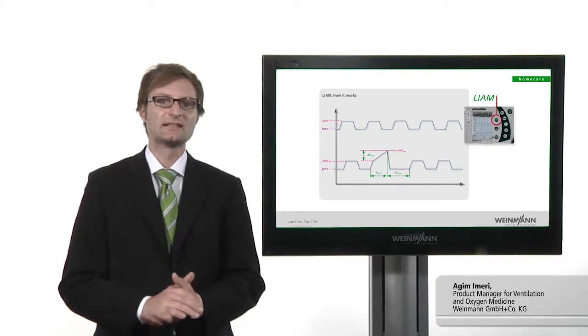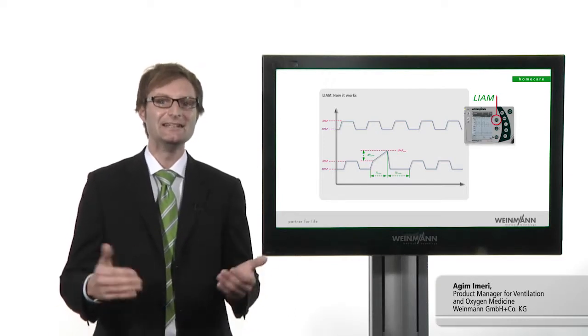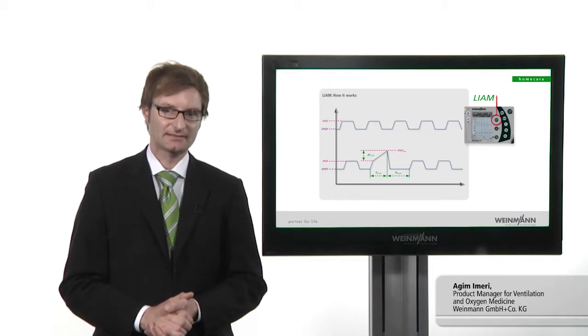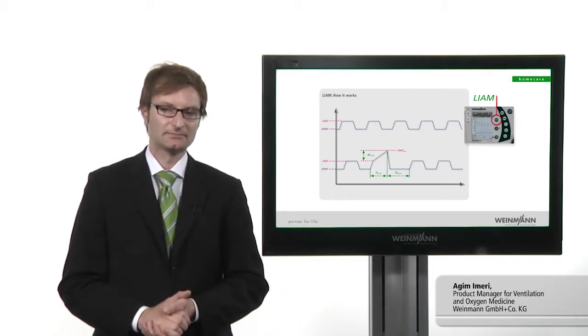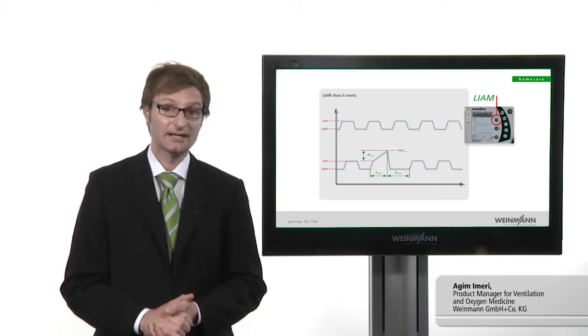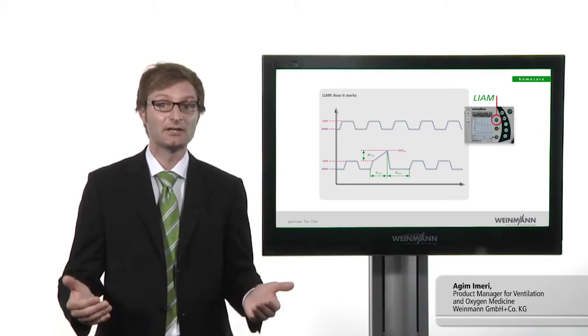During inspiration, an extra pressure, LIAM Delta P, is added to the previously set IPAP. Inspiratory pressure of 20HPA and a LIAM Delta P of 10HPA results in a maximum pressure of 30HPA.